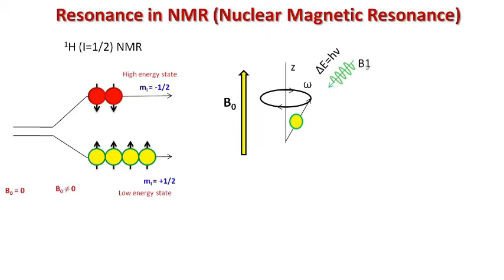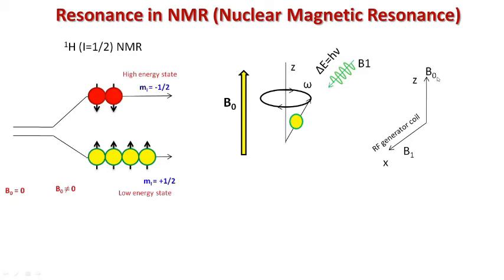The radio frequency radiation is a secondary oscillating magnetic field represented by B1. The magnitude of B1 is several thousand times lower than the applied external magnetic field B0. B1 is applied in the perpendicular direction to the z-axis — for example, in the x-direction — by the RF generator coils. B0 is the static external magnetic field applied in the z-direction.